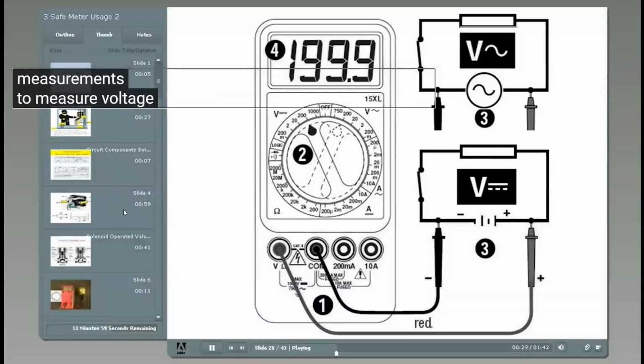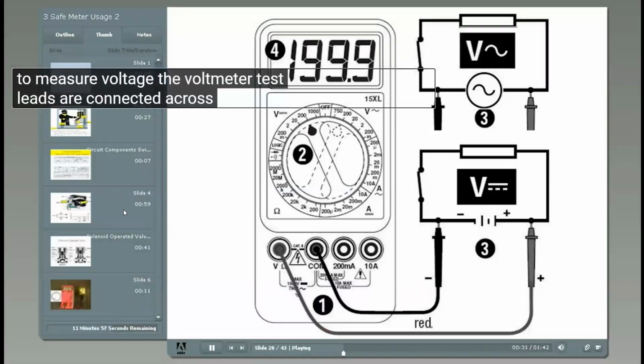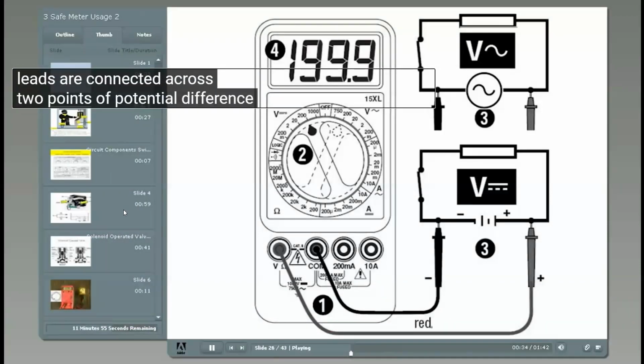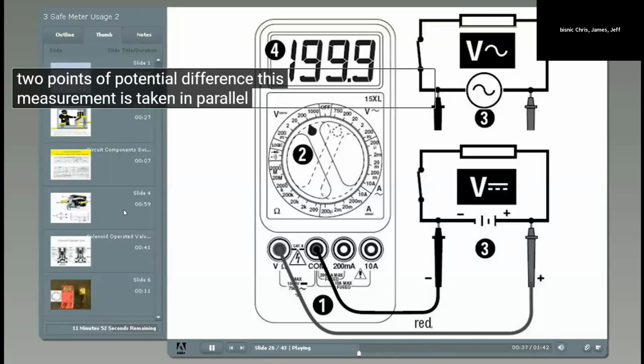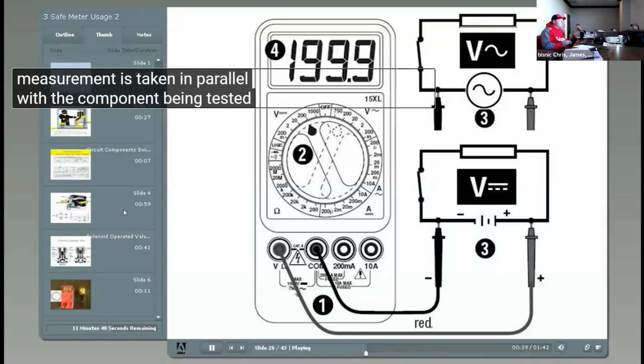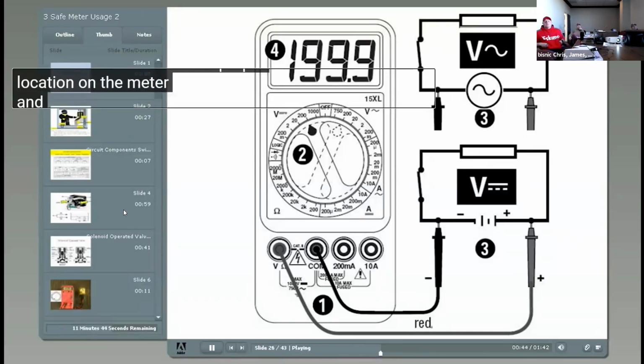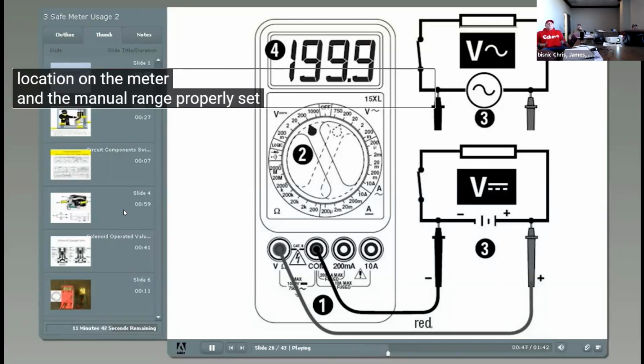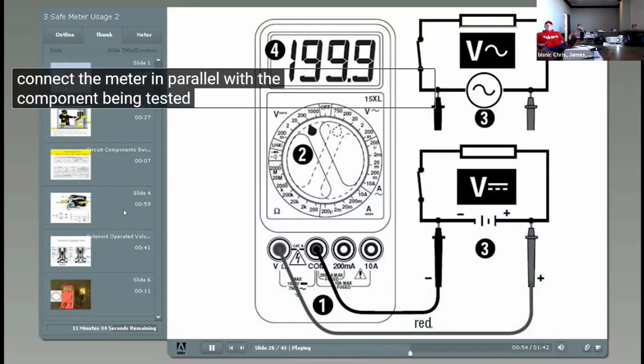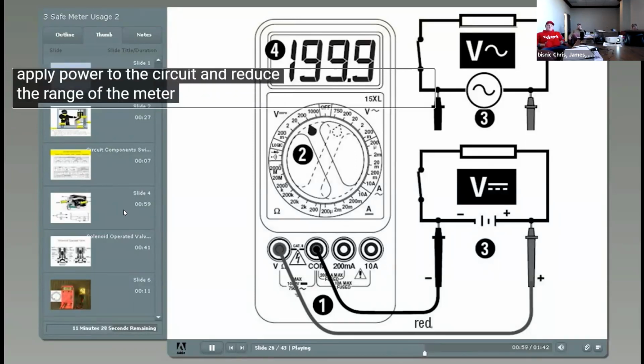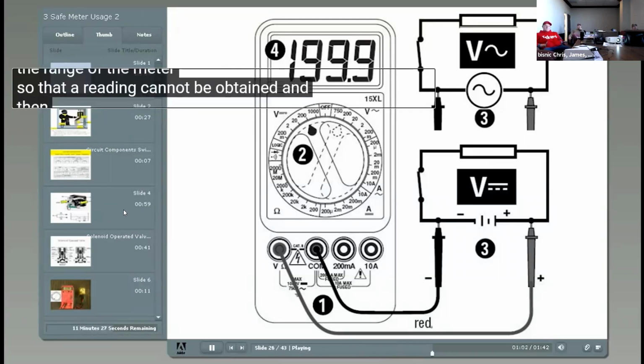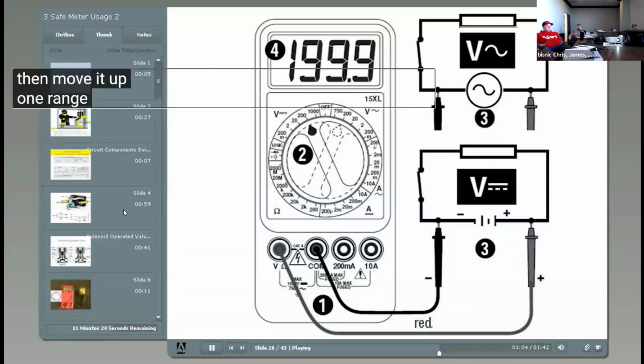To measure voltage, the voltmeter test leads are connected across two points of potential difference. This measurement is taken in parallel with the component being tested. With the meter leads in their proper location on the meter and the manual range properly set to a higher range than that expected to be measured, connect the meter in parallel with the component being tested. Apply power to the circuit and reduce the range of the meter so that a reading cannot be obtained, and then move it up one range.